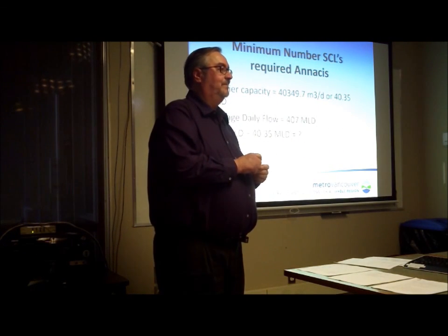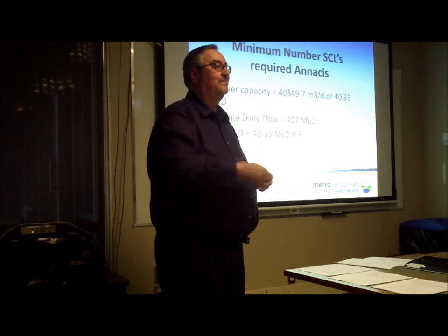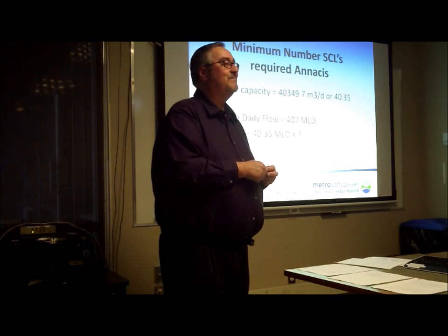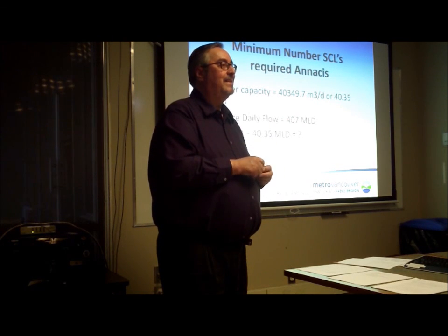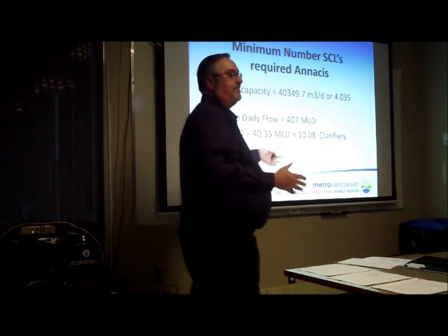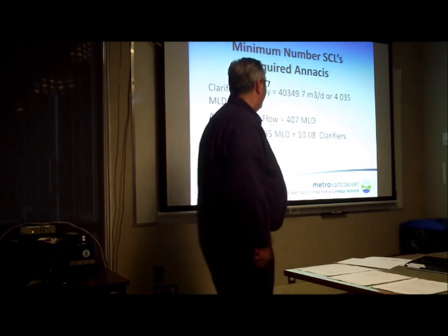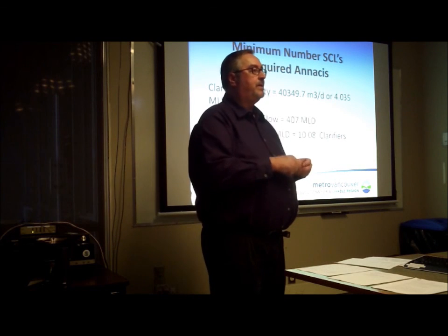So how many clarifiers do we need to treat that flow? Anybody? Yeah, 10. You can't put a portion of a clarifier in service, so if it's over 10, 10.08 clarifiers, yeah, I do 2 decimals in Excel. But essentially 10 clarifiers at Annacis would be enough to treat their flow.